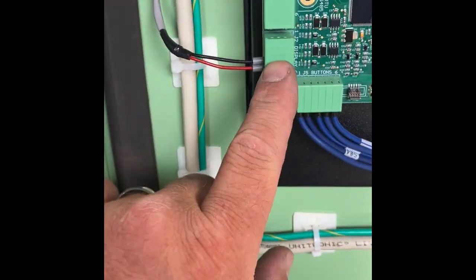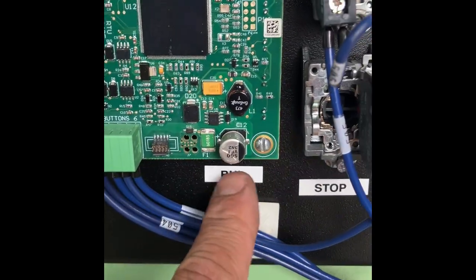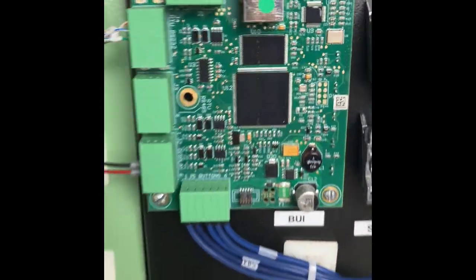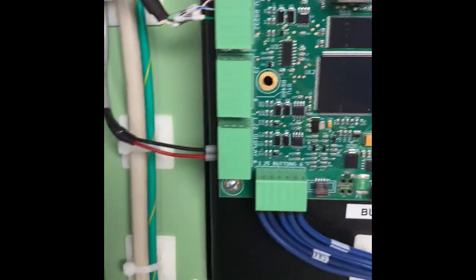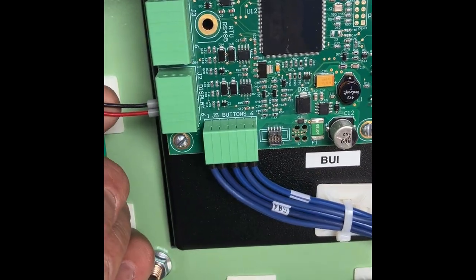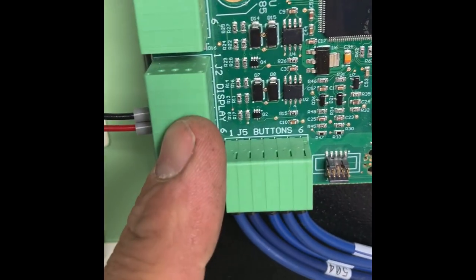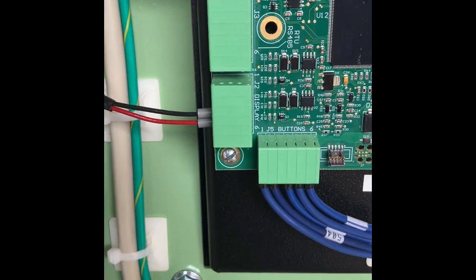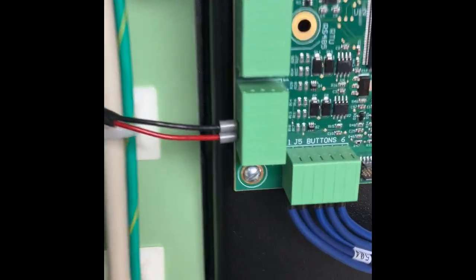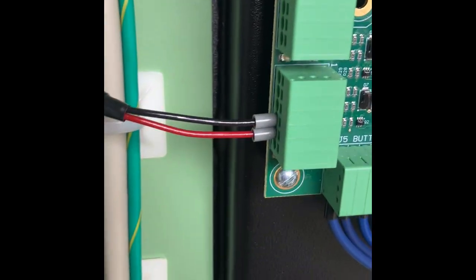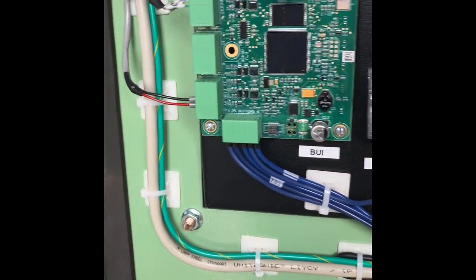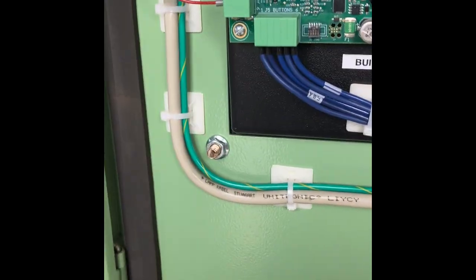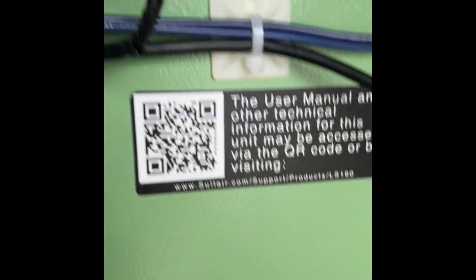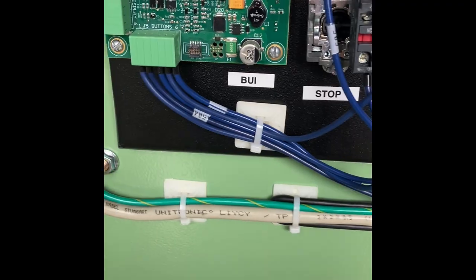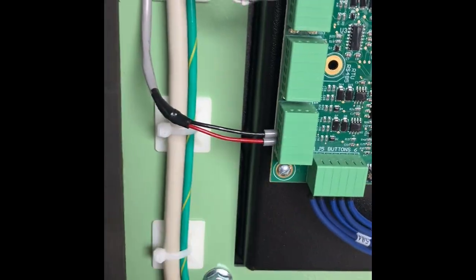Over here, the Modbus wires actually hook into what's called the BUI board - Basic User Interface - and the drawings you'll get from Energair will tell you it goes on J2 RS485 plus and minus. It does not tell you which terminals those are. That information is going to be on the wiring diagram for this particular machine. So you just gotta hit the QR code and pull up the wiring diagram, and it will show you who's who there.